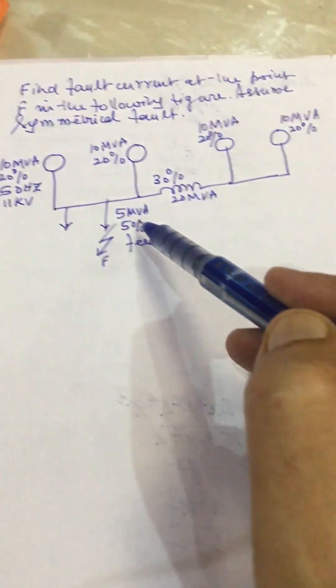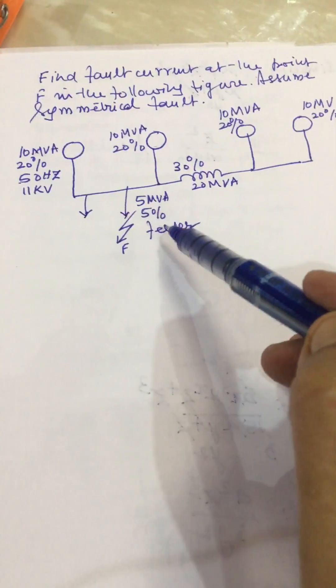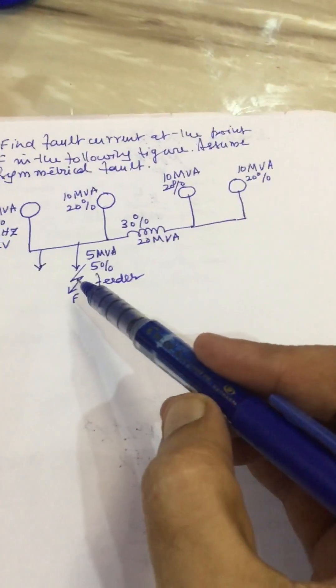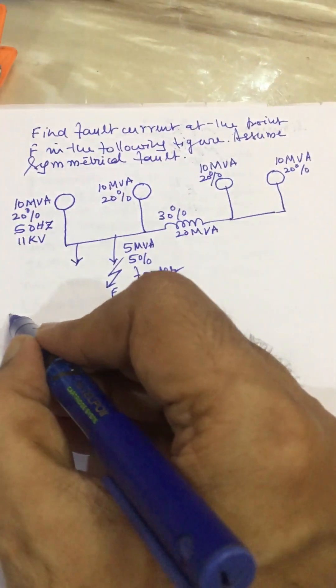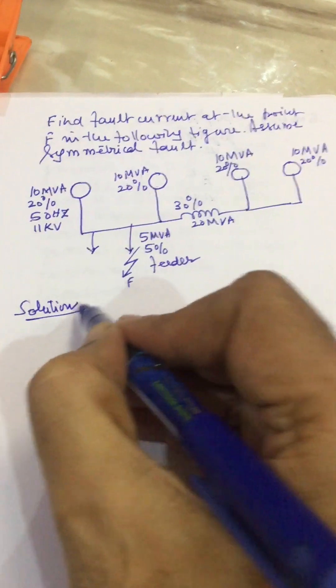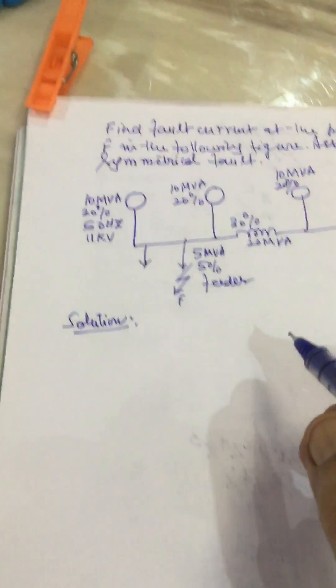And this is our reactance 30 percent reactance at 20 MVA and this is our feeder 5 MVA, 5 percent feeder. Now fault takes place at the point F, we have to find out the fault current. We can proceed to solve this problem as follows.